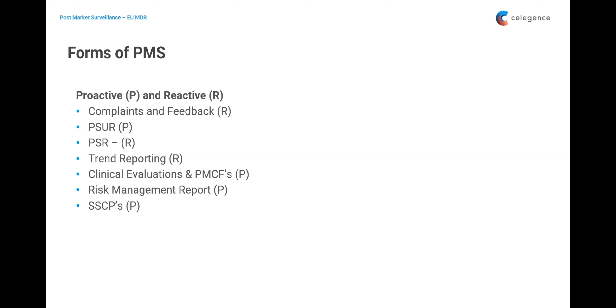Your SSCPs, your summary of safety and clinical performance of your devices for the ones that need it, and I think they are class 3s and implantables, will be proactive. Your SSCPs are not necessarily covered under your PMS in Articles 83 to 92. However, it's stated in Article 32, just after the UDI and EUDAMED articles. You've got SSCPs right there, and that's a proactive form of a PMS that you have to do.